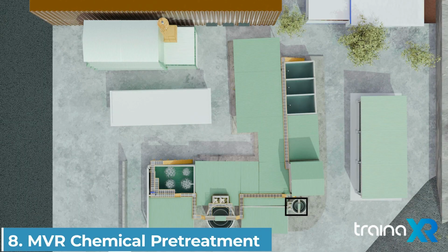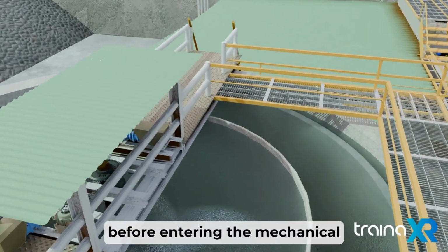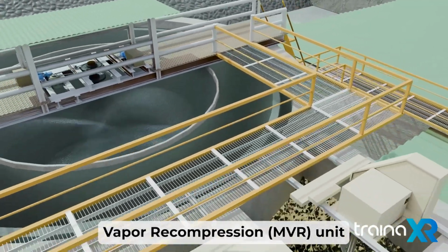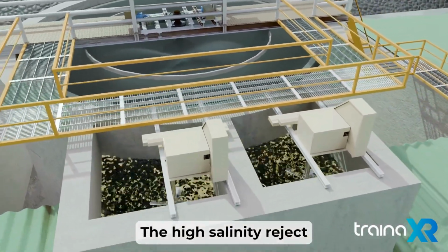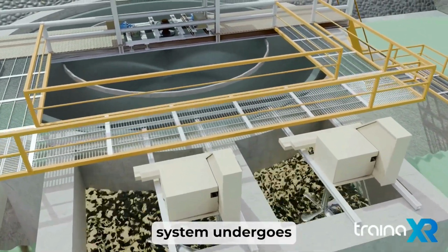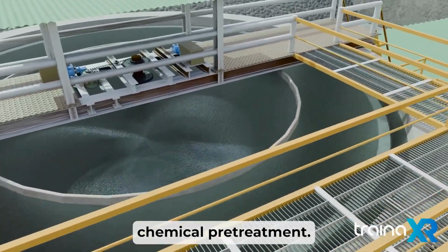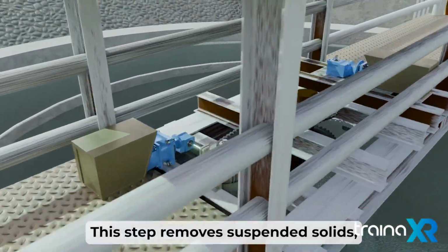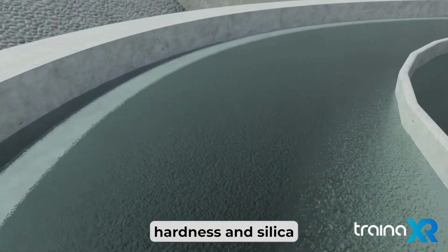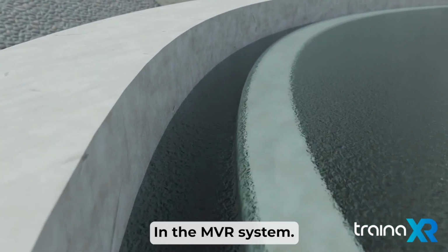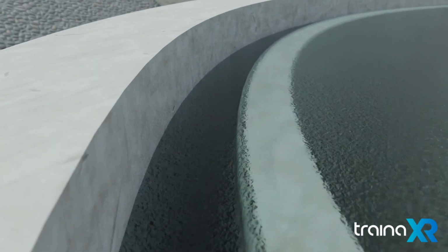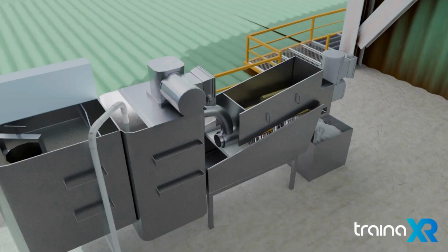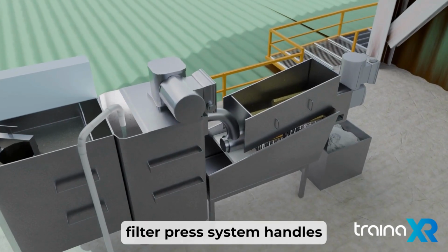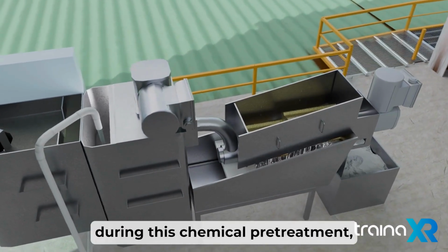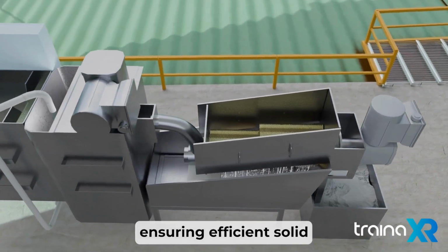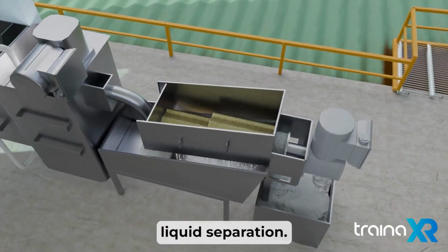MVR chemical pretreatment. Before entering the mechanical vapor recompression (MVR) unit, the high salinity reject from the last stage of the RO system undergoes chemical pretreatment. This step removes suspended solids, hardness, and silica to prevent scaling and fouling in the MVR system. A dedicated filter press system handles the sludge generated during this chemical pretreatment, ensuring efficient solid-liquid separation.